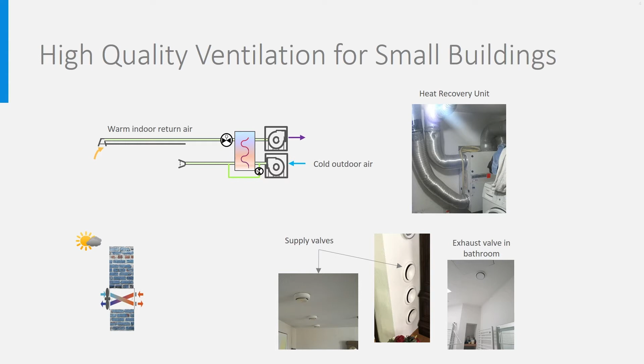Unfortunately, in many of these systems, there is only one central flow rate control, meaning that all rooms are equally ventilated. But in general, at night, people are in the sleeping rooms and not in the living room, and conversely. A zone control, for instance one zone being the sleeping rooms, the other one the living room and kitchen, is better but does not account for the flexible use of rooms. Sleeping rooms are often used as study rooms, so in the end, control per room is much better, like this.